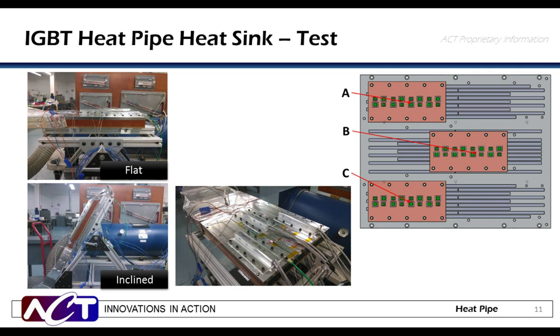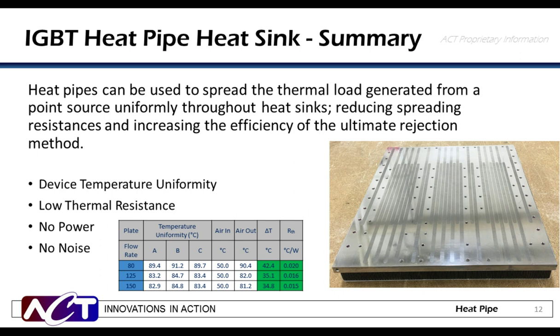Testing was performed in both flat and inclined orientations, with heater blocks attached to simulate the loads. In summary, heat pipes can be used to spread thermal loads generated from point sources on a heat sink uniformly throughout the base. This reduces spreading resistances and increases the efficiency of the ultimate rejection method — in this case, improving fin efficiencies drastically for the folded fin design. You get device temperature uniformity and low thermal resistance with no additional power or noise, and testing results confirmed we hit our goals.